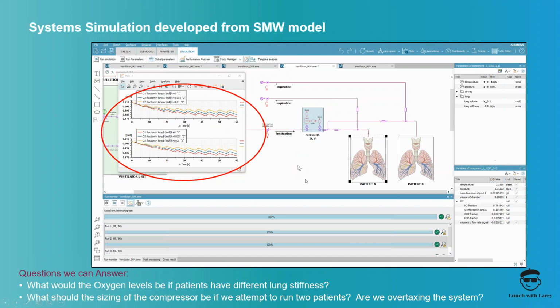How big is the compressor for the ventilator? What's the stiffness of the patient's lungs? In this case, we built out 2 patients with different lung stiffnesses. What that allowed us to do is start to model what we believe the O2 level of the air going into the patient is going to be based on 2 patients that have different capacities, maybe different stiffness of lung, and what we would expect to see in a performance degradation if we put 2 patients on the system in parallel instead of just one, which of course would lead us to new design options. We'd try to figure out how to valve between the 2 patients to assure that they both get an appropriate level of oxygen.